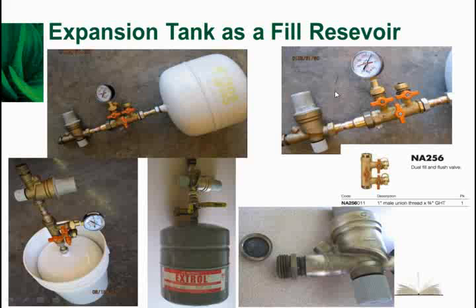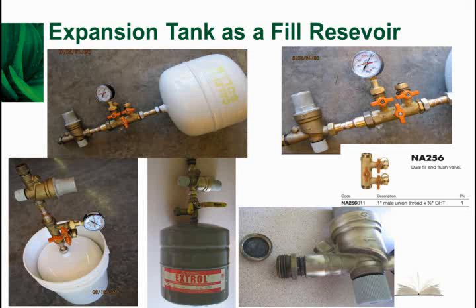Another little way, if you want to take some fluid along to a job with you, a fluid that can be glycol that you can pump in here. If you have some cleaner or chemical that you want to take to a job and you don't want to take a pump, you don't want to take a drill motor or any kind of electric pump, you can actually take just an off-the-shelf expansion tank. This is one of our Caleffi solar expansion tanks here. And just put one of those valves that I just showed you, one of our fill purge valves, screw it right onto the nipple on the top of that tank.